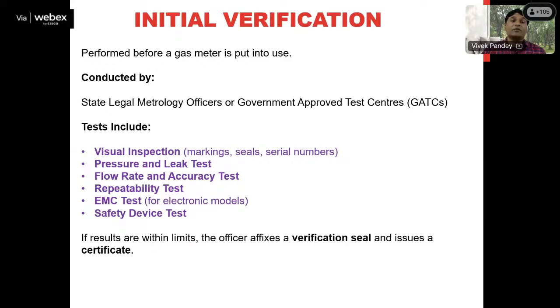Then we will also perform the flow rate test and accuracy test. Then we will check the repeatability test. As I already mentioned, it is the check of the consistency of the gas meter, whether it is consistent or not. Then we also perform the electromagnetic test, then the safety device test. After these tests are performed and the instrument is found satisfactory, a verification seal is applied to the measuring instrument, and it is issued with a certificate.